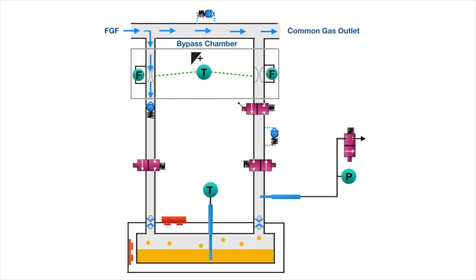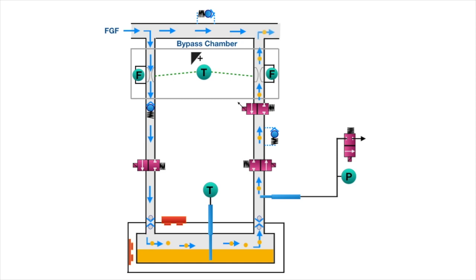As the vaporizer is opened, a designated volume of fresh gas flow flows into the cassette inlet. As the vaporizing chamber is inside the Aladdin cassette, the carrier gas has to pick up the saturated vapor molecules. It then proceeds through the outlet flow route and joins the common gas outlet. Job done — the vapor reaches the common gas outlet, just like our basic vaporizer design.